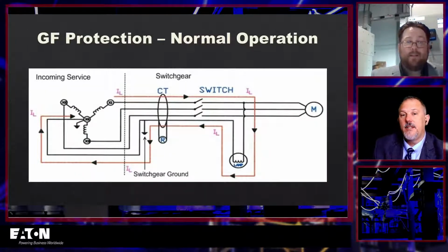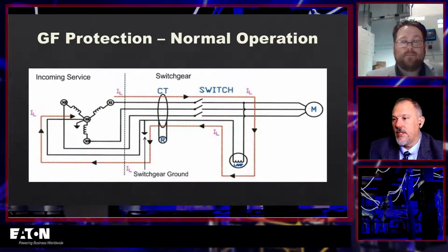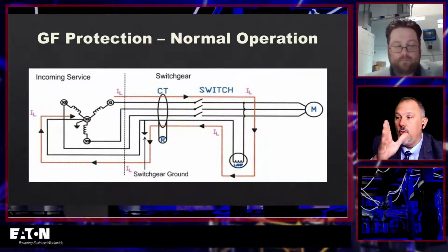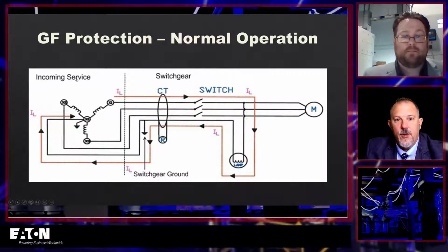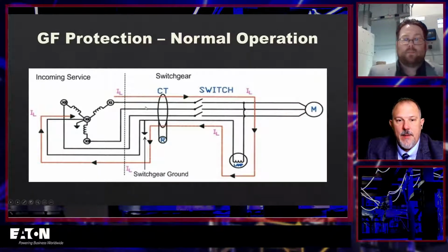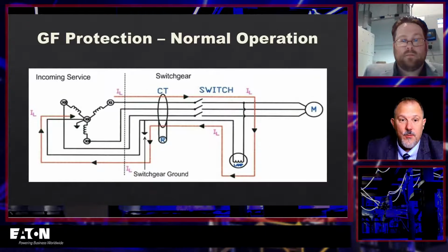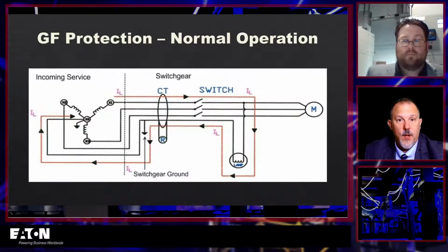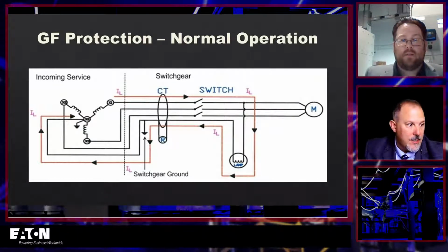And then, this is just a slide that talks about what you explained. You have all the current going through this CT, it's coming back. So as long as all your currents stay in the conductors that are going through that circle, which would be the current transformer, then you know everything's copacetic. It all adds up to zero. But the moment it goes outside of that path and finds its way back to the equipment grounding conductor, that's when we say all heck breaks loose, right?